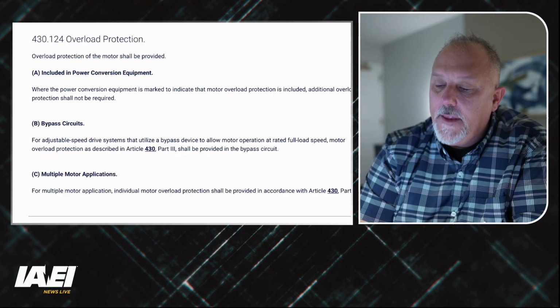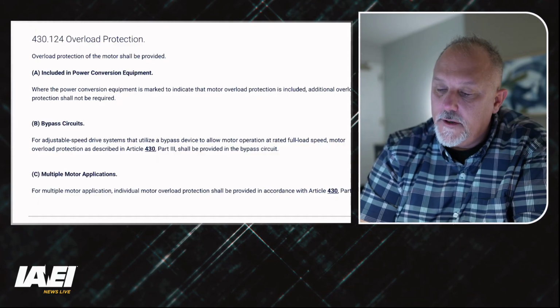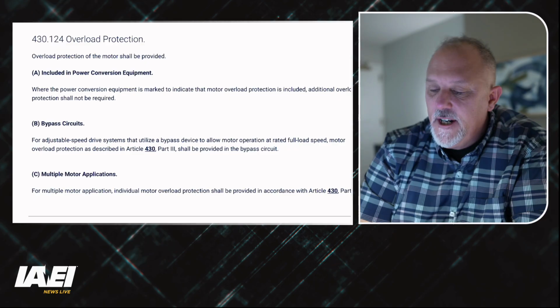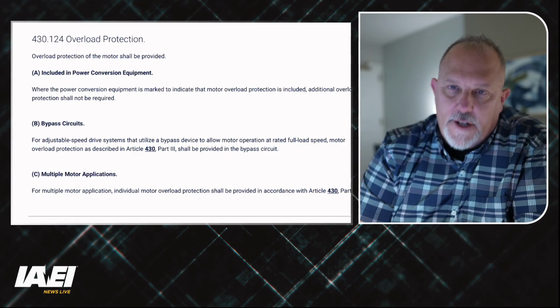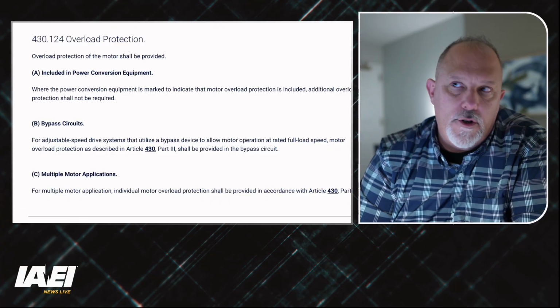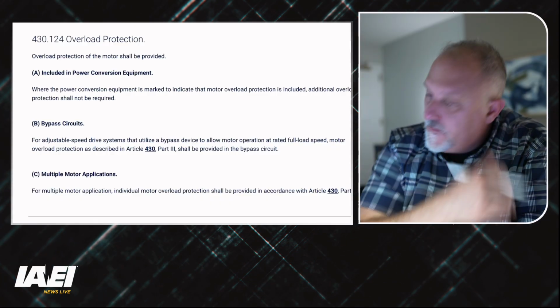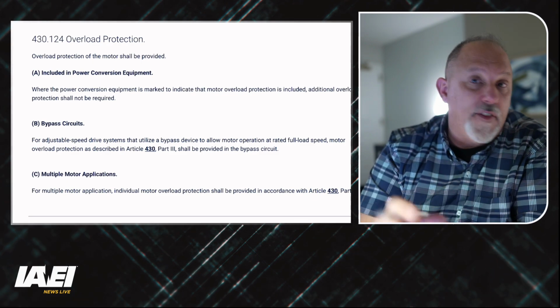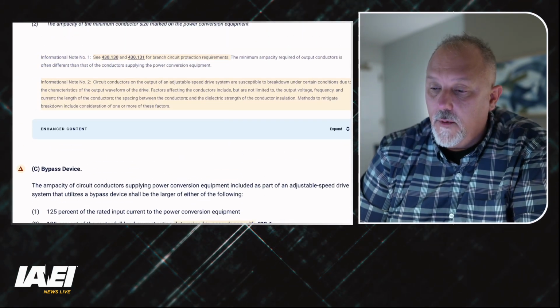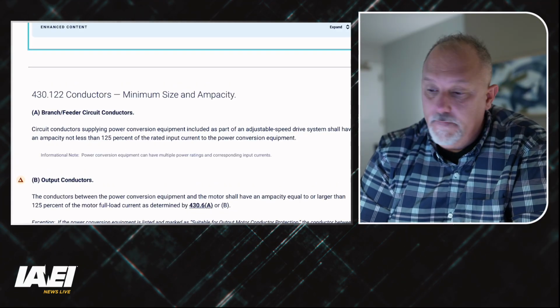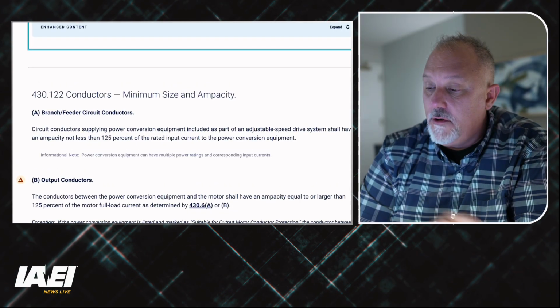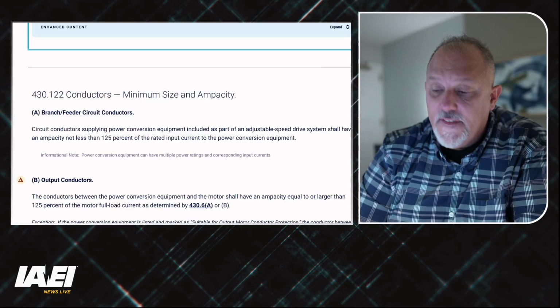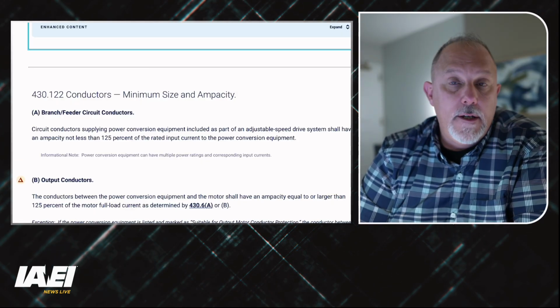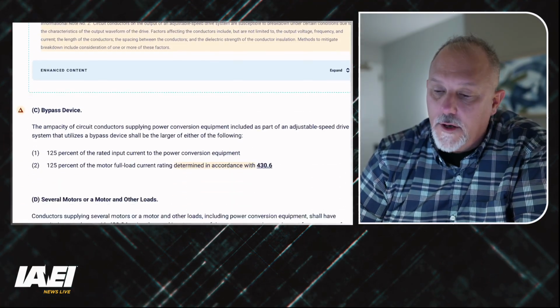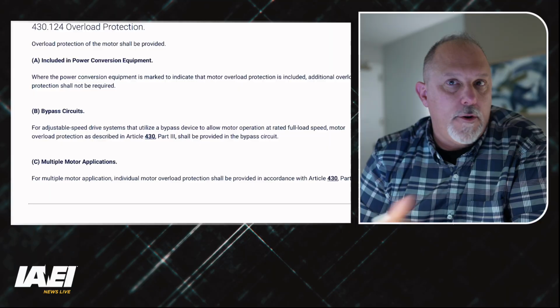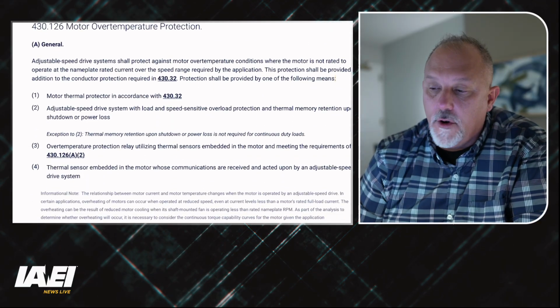And then they deal with the multiple motors applications. Each of those motors has to have overload protection. You're not going to have one overload protection for multiple motors. Each motor is going to have its own overload protection. So 430.124 has nothing to do with the input conductors that were selected up here. Circuit conductors supplying power conversion equipment included as part of an adjustable speed drive system have to have an ampacity not less than 125% of the rated input current. So those are the conductors feeding the drive, and the overload is dealing with overload protection of the motor, not the drive itself. Then you have motor over temperature protection.